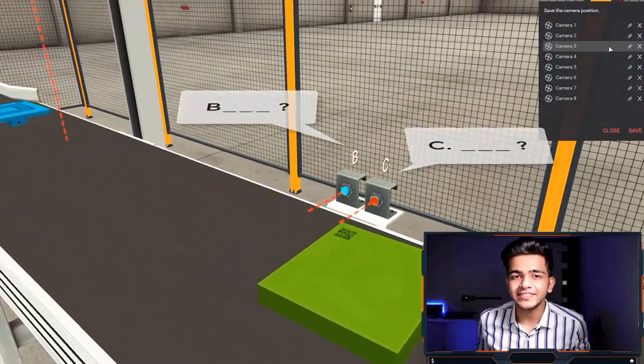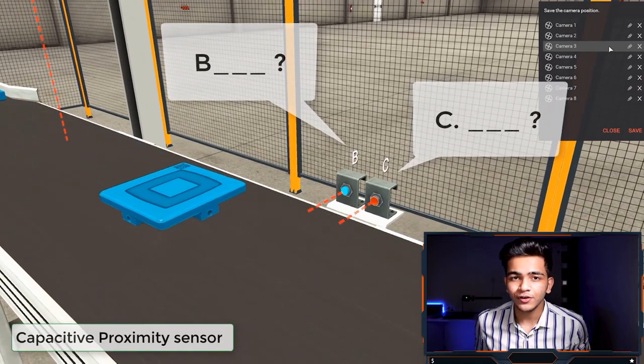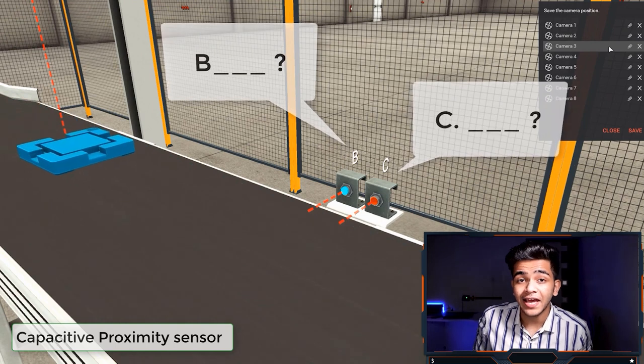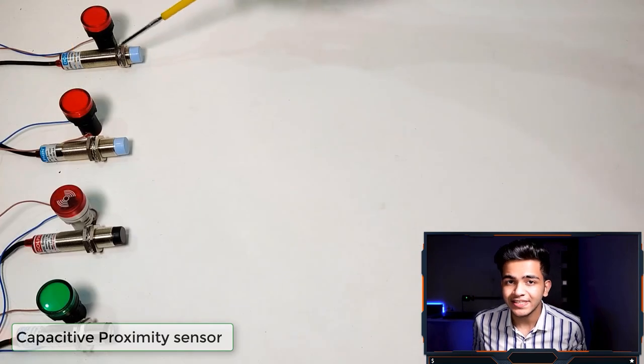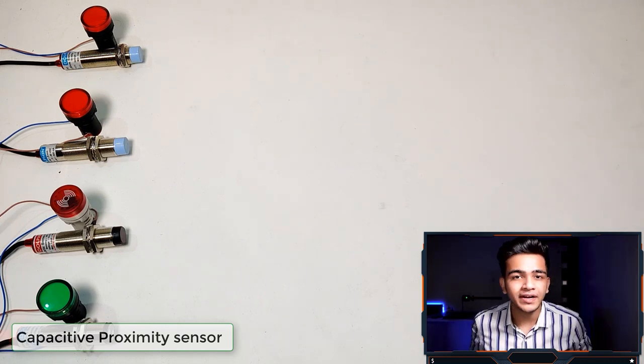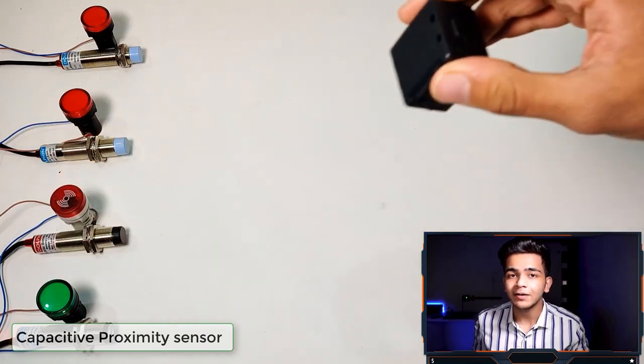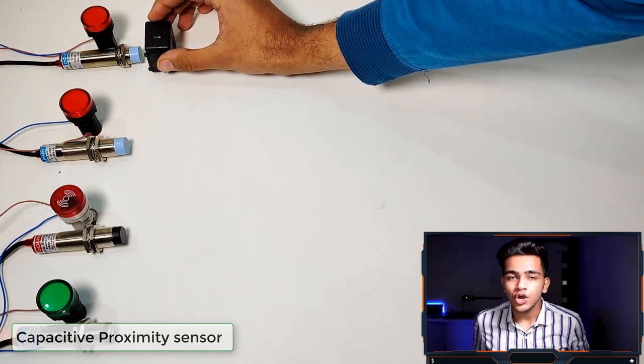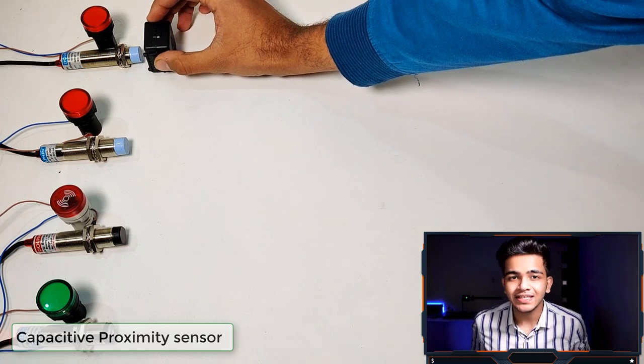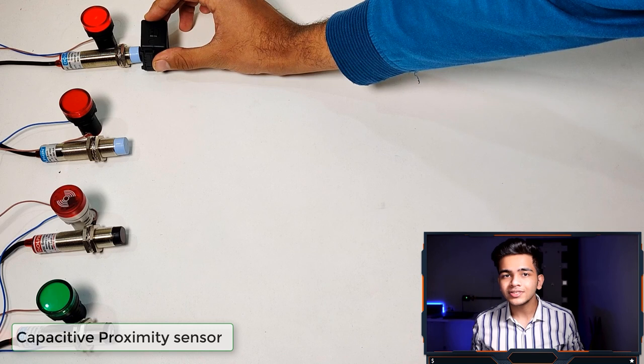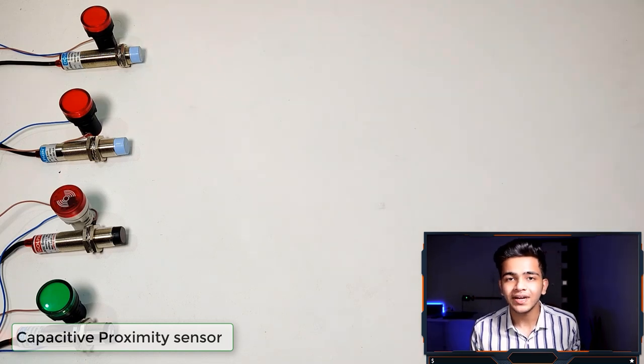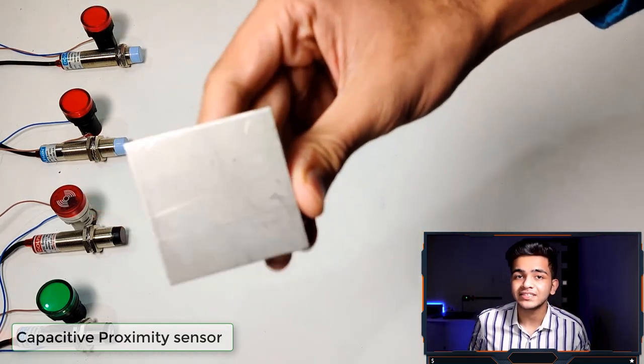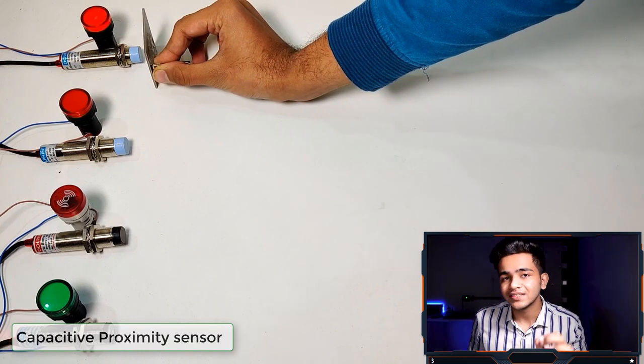The second sensor, Sensor B, is a capacitive type sensor. A capacitive sensor will detect both metallic and plastic targets. When any target with a certain density — whether it be liquid, powder, or any sufficiently dense material — comes in range, the sensor will give an output. You can see how the sensor responds to different targets, including metallic ones. Unlike inductive sensors which will not detect plastic targets, capacitive sensors detect both metallic and plastic targets.